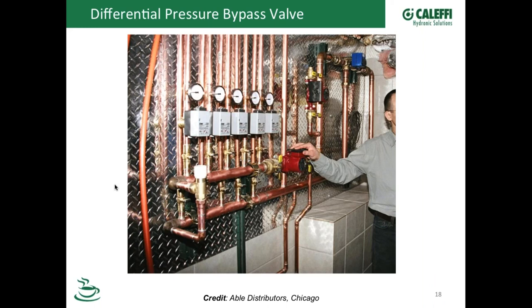On those differential pressure bypass valves, they were more popular in history than they are currently, just because of variable speed circulators. But one thing to be really careful of with those differential pressure bypass valves, like ours is adjustable from 2 to 10 psi, and you've got to be really careful. We get a lot of calls about strange applications, whether it be breweries or whatever the case may be, and they want to use this for chilled water, and they're using a high head circulator. If you have a circulator that produces more than the maximum limit, that threshold of our 519 series, then there's a chance that you're going to be always bypassing. It's never going to shut off completely, and so you've got to be really careful with that. Our differential pressure bypass is more designed around residential applications, but just something to be aware of when you're picking one out.